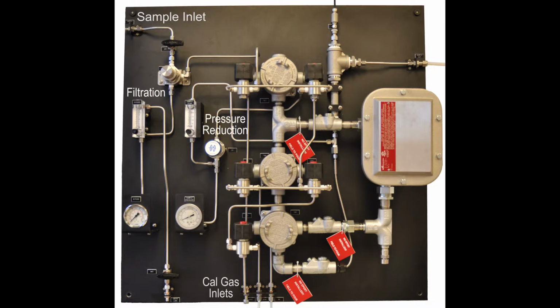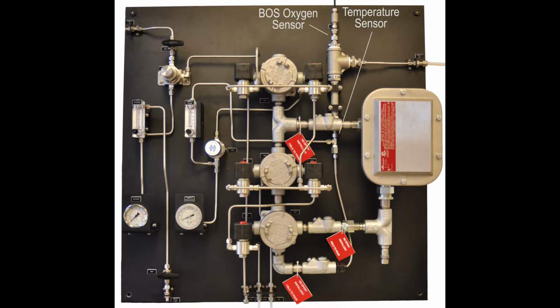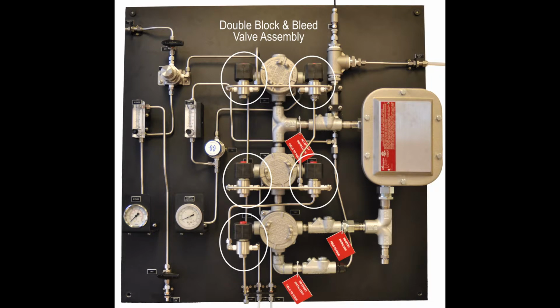The tubing routes the gas to a flow cell, where a BOS oxygen sensor and temperature sensor are mounted. All calibration gas flow is controlled by these solenoid valves. This is a double block and bleed arrangement. It's designed so the process gas cannot contaminate the cal gas and vice versa. The solenoid valve is a fail-close design.